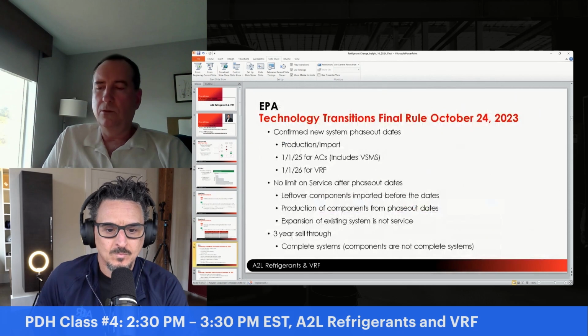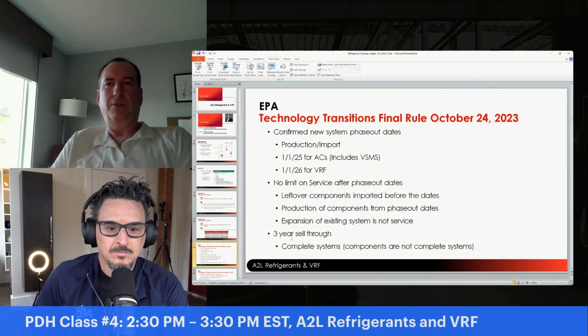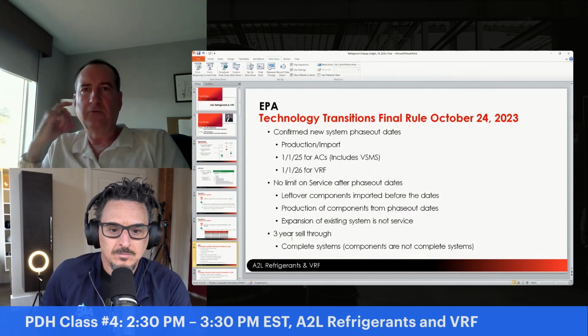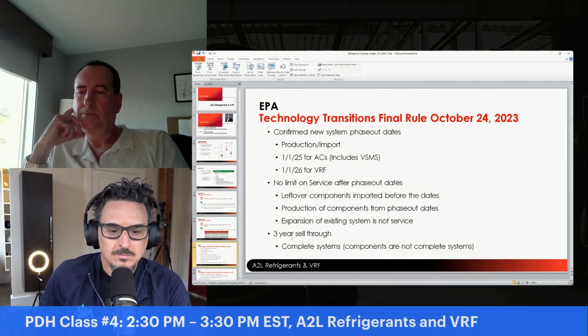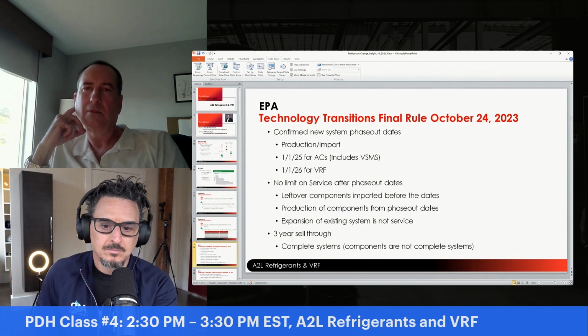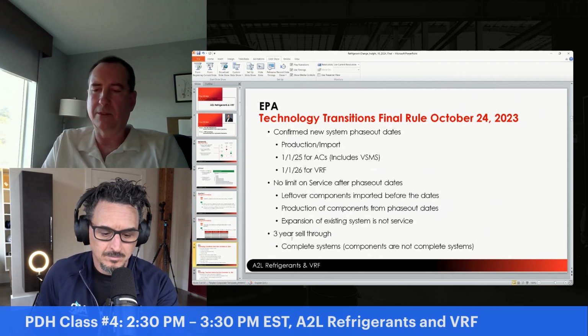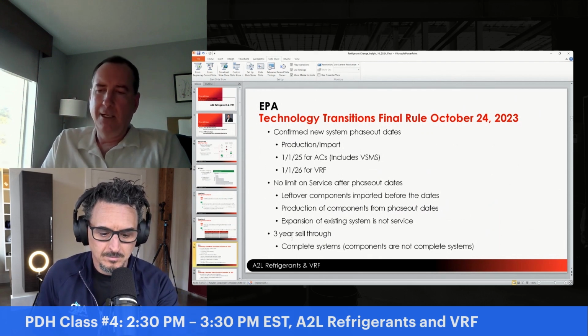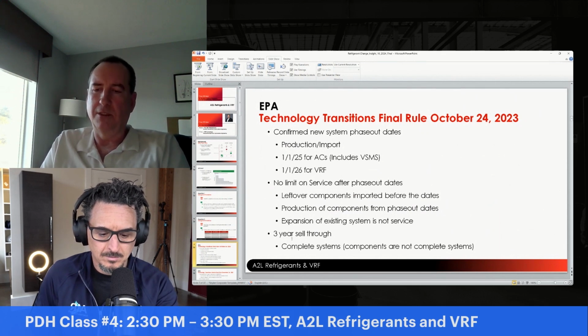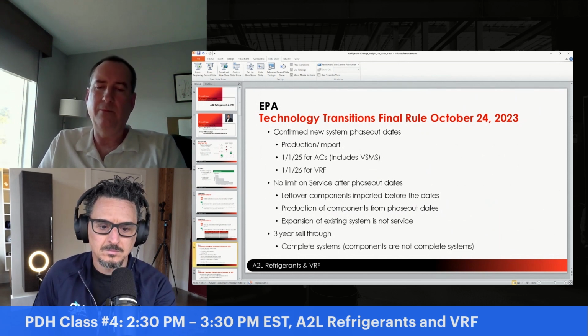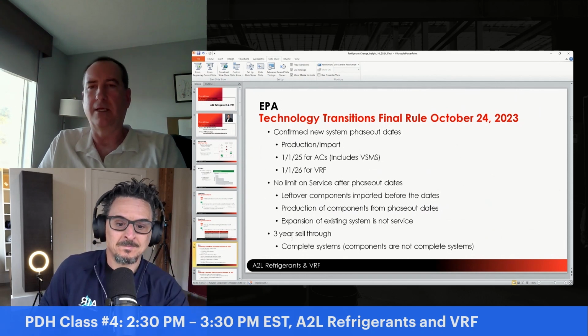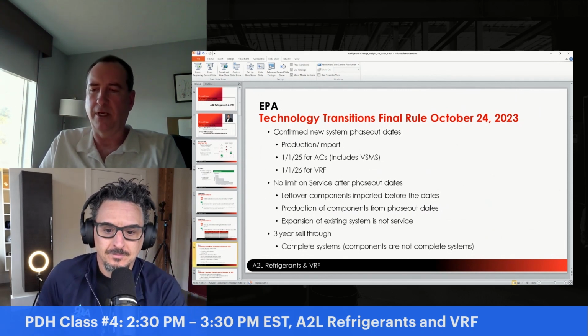This brings us to some of the EPA technology transitions they are publishing. This confirmed the rule that was done in October last year, confirming these new system phase-out dates of the higher GWP refrigerants in new equipment, and it defined the production dates where products could no longer be used for new systems. For us, we compare the import date to these phase-out dates since our stuff is manufactured elsewhere.